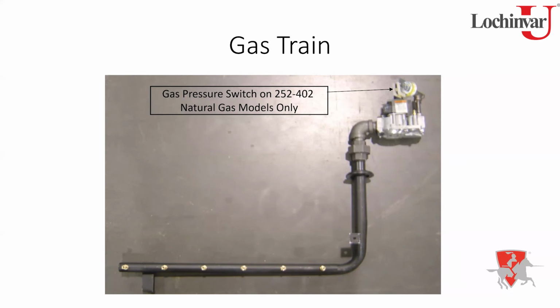So because of that, that's why that gas pressure switch is there, to shut the heater off if you hit that number. That's the only reason for the switch. It is an automatic reset, so there is no manual reset to it. If for some reason you wanted a manual reset low gas pressure switch, that could be provided, but in most cases that's generally not a requirement for anything under 400,000 BTUs.